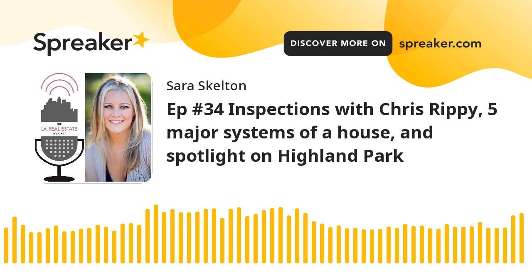We see it quite a bit. It is almost a daily event for us. Somebody wants to add another run to their house, maybe put lights in the garage or something, and they go, I'm out of breakers, so I'll just add another one in this one.